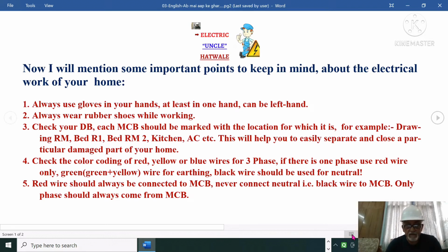Red wire, number 5. Red wire should always be connected to MCB. Never connect neutral, that is black wire, to MCB. Only phase should always come from MCB, not neutral. Neutral should come from the link. If you reverse it, even after putting off your MCB, there will be current in your socket, plug, or somewhere in the switch. You will think that you have put off the MCB and there will be no current. Some electricians used to make such mistakes. That is very risky, so take care of that. Phase should come through MCB.